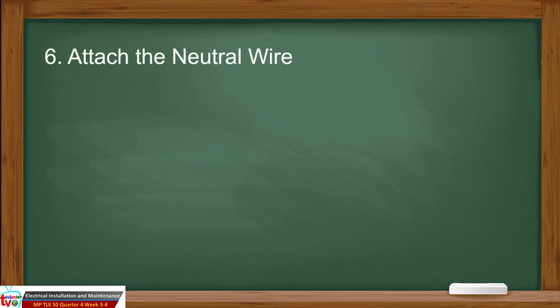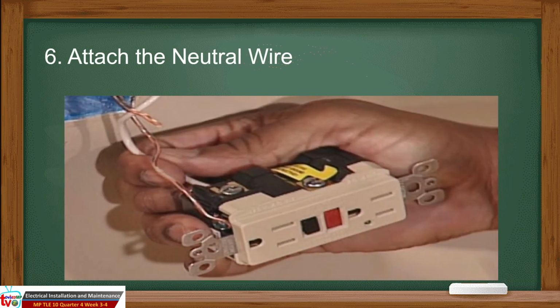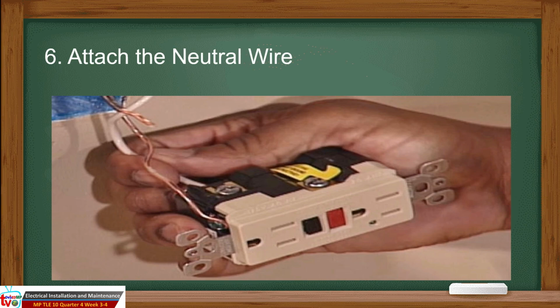Attach the neutral wire. Note that the GFCI receptacle has two holes in the back. This is called a stick-in receptacle. Starting with the neutral wire, push the end of it into the hole on the side with the silver screw. Tighten the screw to hold the wire. Repeat with the hot wire, attaching it through the hole on the side with the brass-colored screw. Tighten the screw.